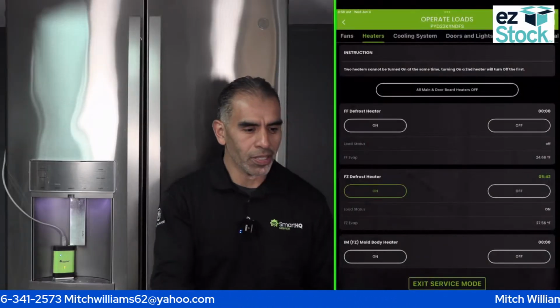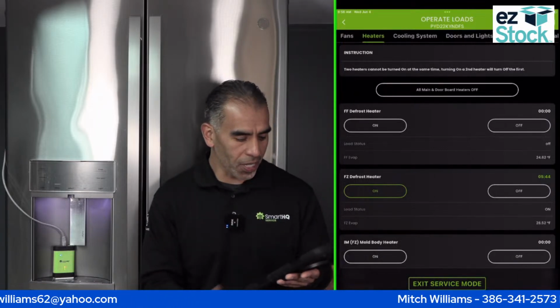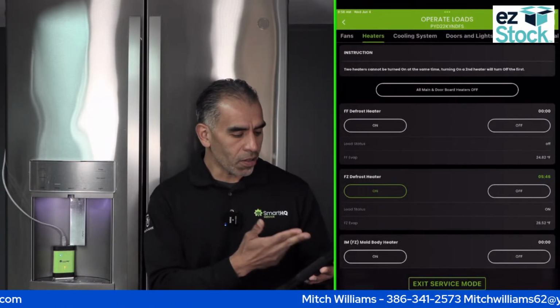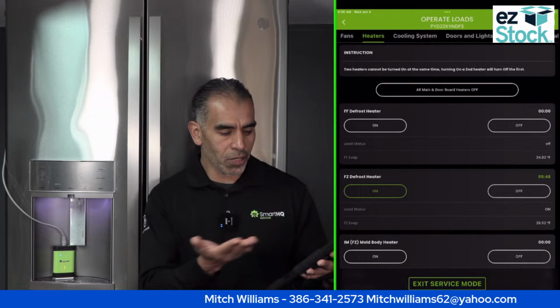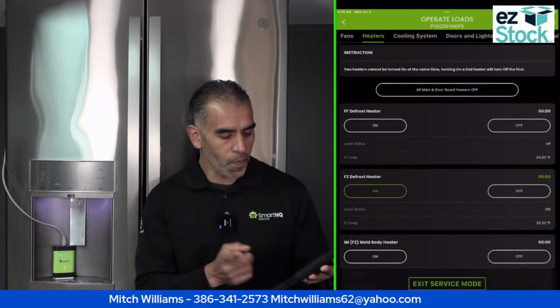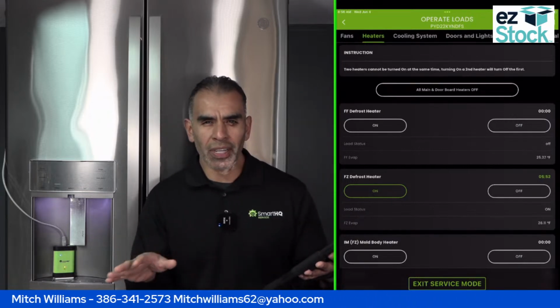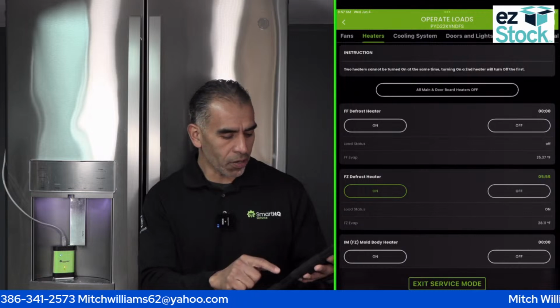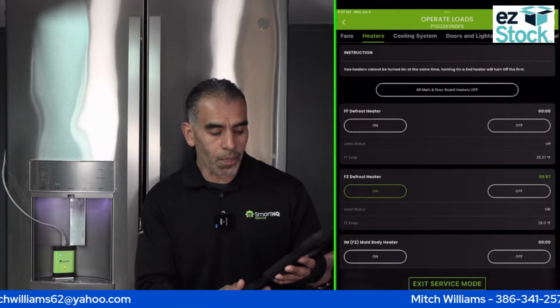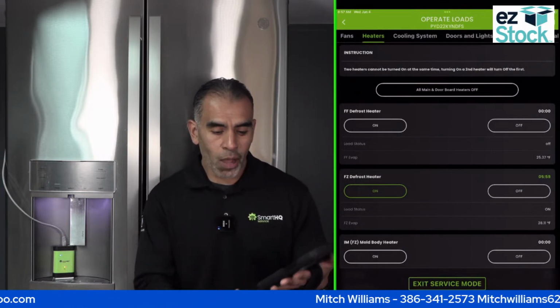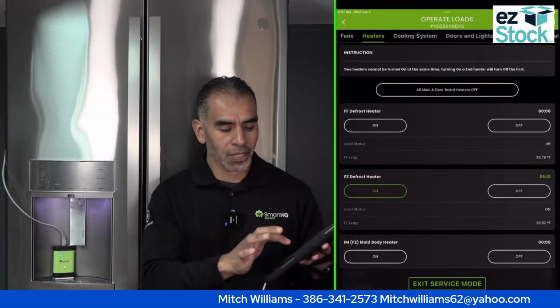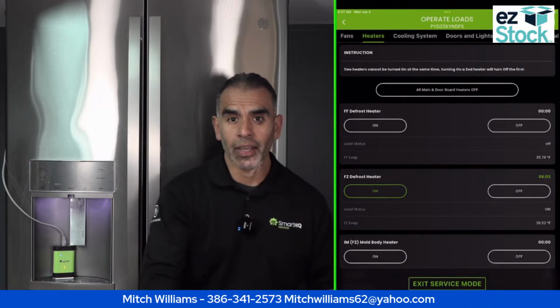All right, so let's take a look at our friend over here—what's going on with the temperature values? And whoa, here we can see clearly: the freezer defrost heater has been on for about 5 minutes 48 seconds, roughly 6 minutes, and it already went from 11 or 13 degrees all the way up to 28 degrees. Now it's 28 degrees, but even if I stop the test, the heater is still hot.